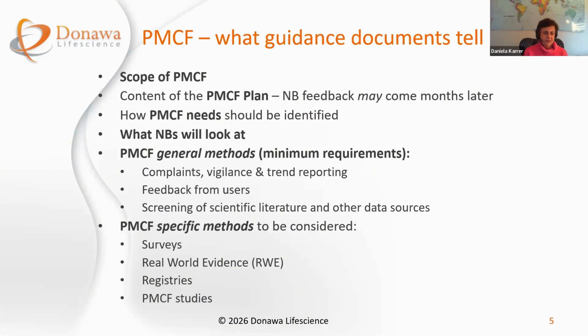I've put here some distinction between the PMCF general methods and the specific methods. Well, the general methods are expected as kind of default type of activity that takes place for all medical devices. So it's complaints, vigilance, spontaneous feedback from users, review of the scientific literature on the device or similar, etc. There is no debate, I think, on this part.